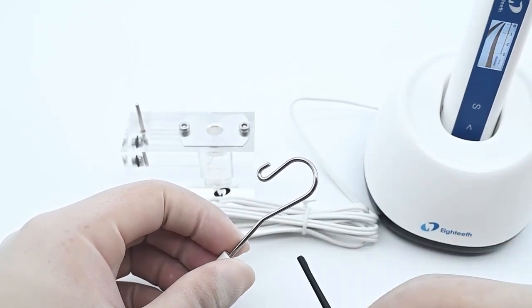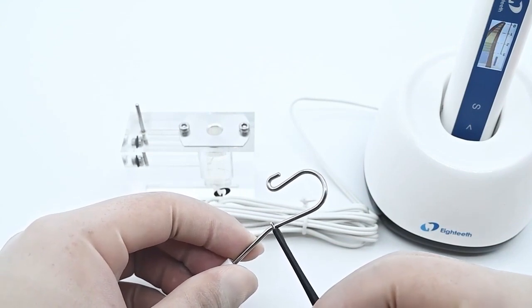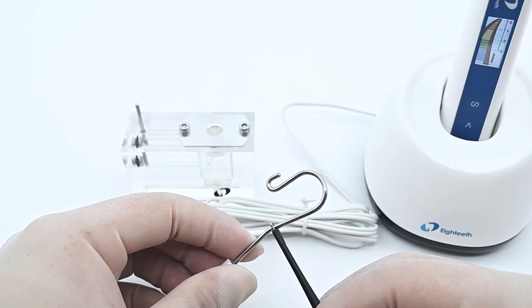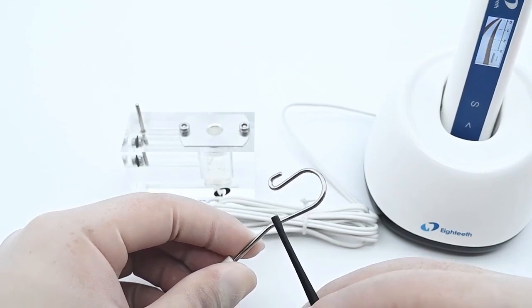Check the connection of the measuring wire, lip hook, and file clip before each use of the Apex Locator function. Confirm that all the value bars will be displayed on the screen.